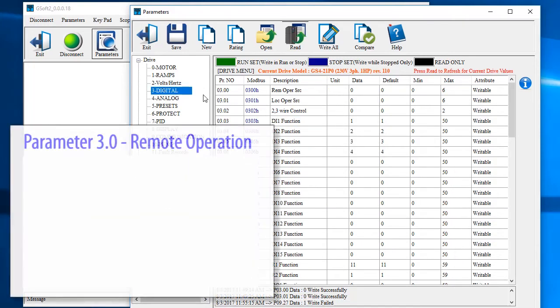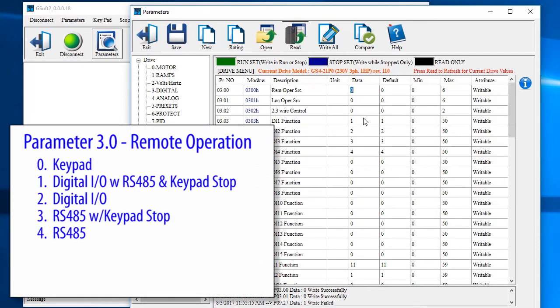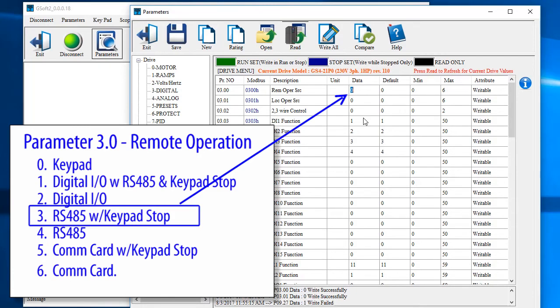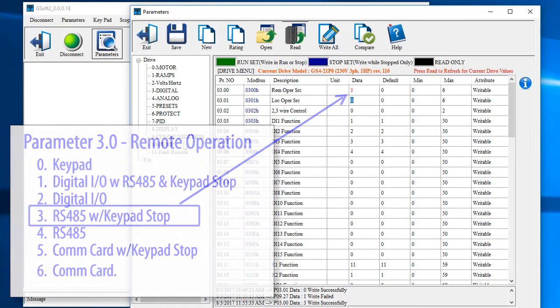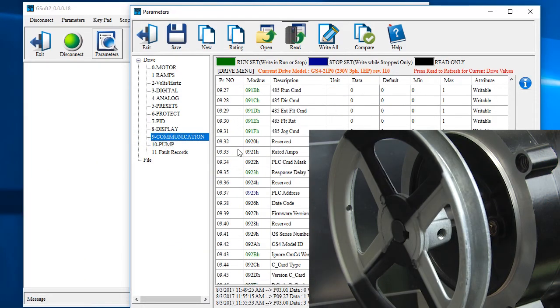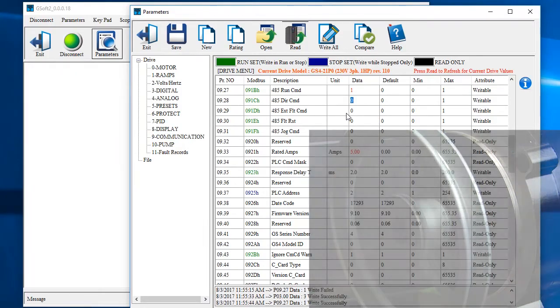With parameter 3.0 we can tell the drive to accept run commands from the keypad, a digital IO, the RS-485 port or a com card. We want this one that leaves the keypad stop enabled so we enter a 3 in parameter 3.0. Now if we go back to parameter set 9 and enable the run command, sure enough the motor runs. Perfect.